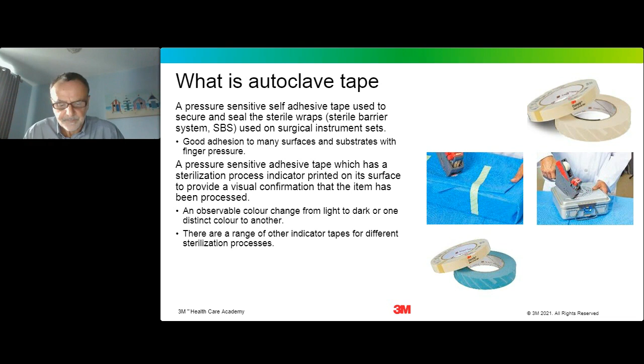So why do we need and use autoclave tape? Well, many reusable surgical instrument sets are wrapped in single-use or sometimes reusable flexible packaging, which are also called sterile barrier systems. So the purpose of autoclave tape is to secure the packs wrapped in these flexible materials to create a sterile barrier layer. With the presence of a process indicator, the tape provides not only a securing mechanism, but also an indicating mechanism as well.